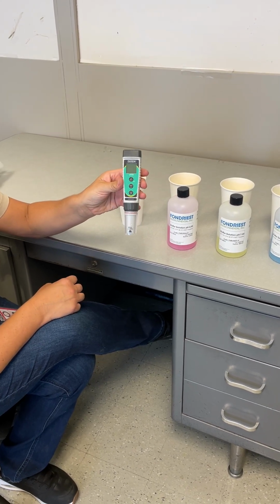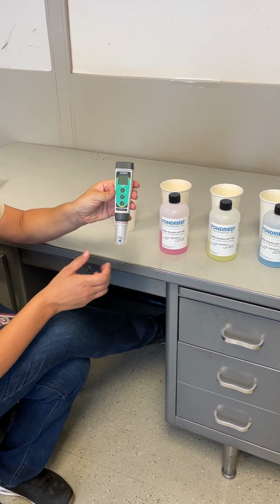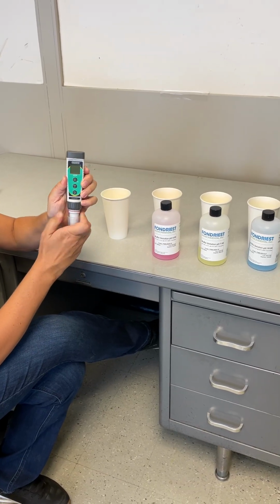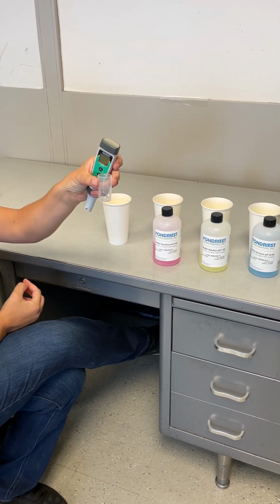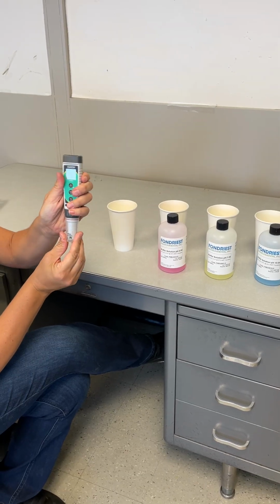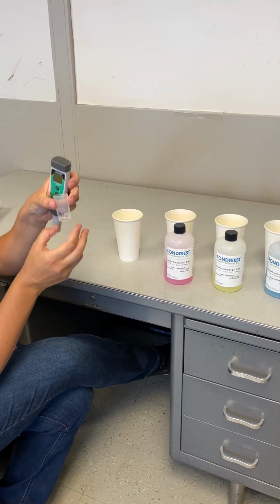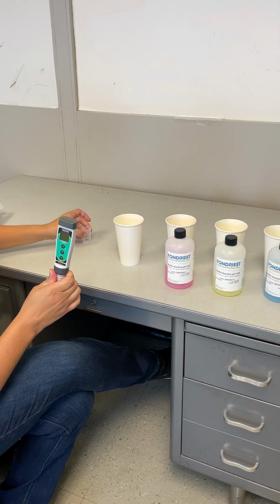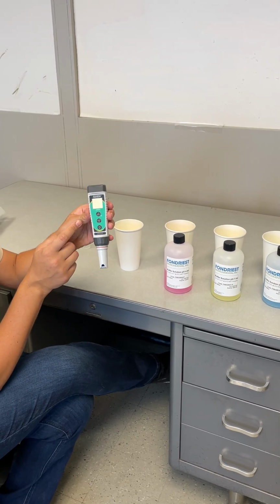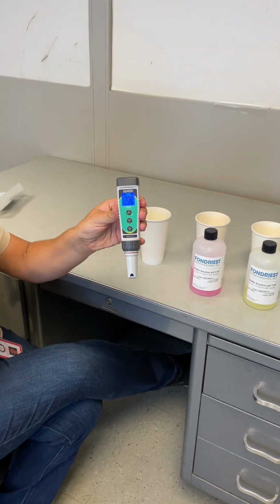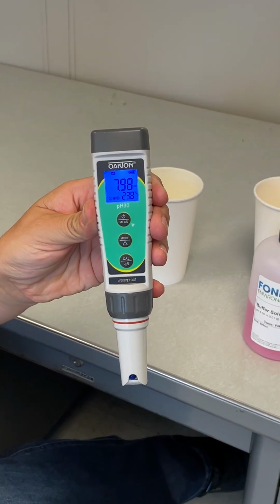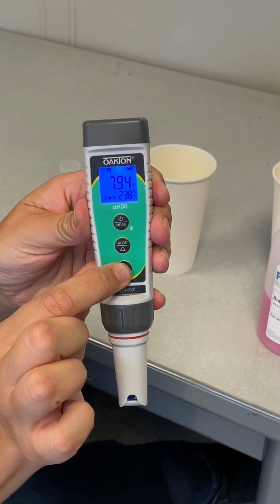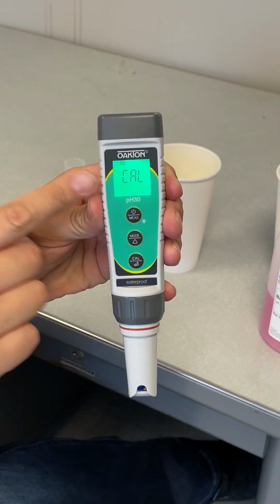Okay, quick calibration video for our Oakton pH meter. So I just wanted to firstly say that you can actually store water in the cap here, and it's good for the tip, so you can just keep water in there and dump it out every time after you use it. So to start, you just turn on your pH meter, and then to start calibrating, you long press the calibration button until it says calibration.